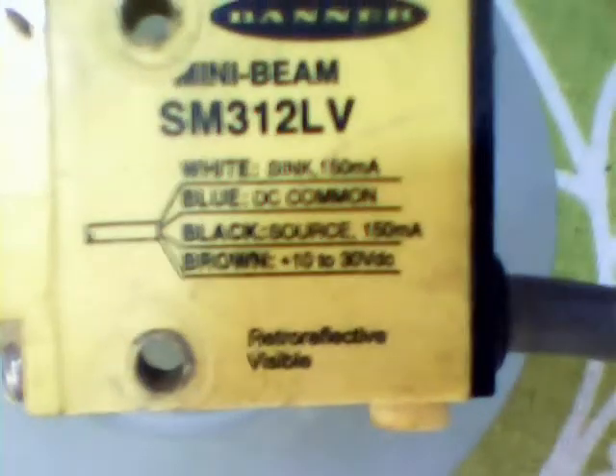And this is a sink type of PLC. So the inputs will go low whenever there's a high-state voltage goes to 0. That's how the PLC is wired up, it's sinking inputs. Which is a good thing because if it's a short circuit, it means that they're not active.